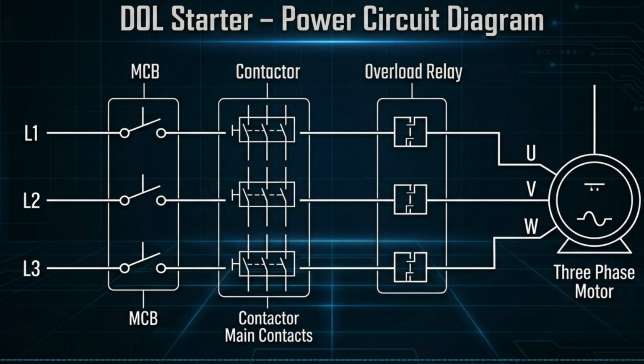After the circuit breaker, the three-phase lines pass through the main contacts of the contactor. The contactor is an electrically operated switch that connects or disconnects the power supply to the motor. When the contactor coil is energized through the control circuit, these main contacts close and allow the electrical current to flow toward the motor. Next in the circuit, we have the thermal overload relay, also known as OLR. This device is very important for motor protection.